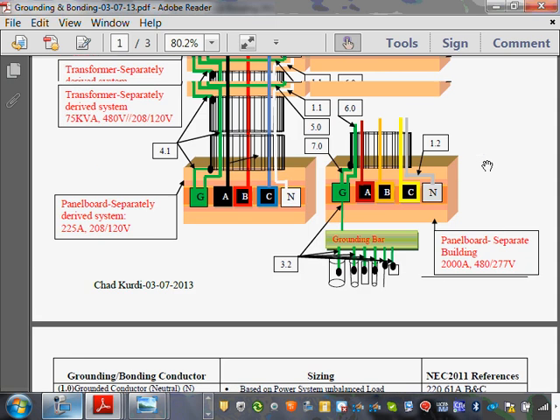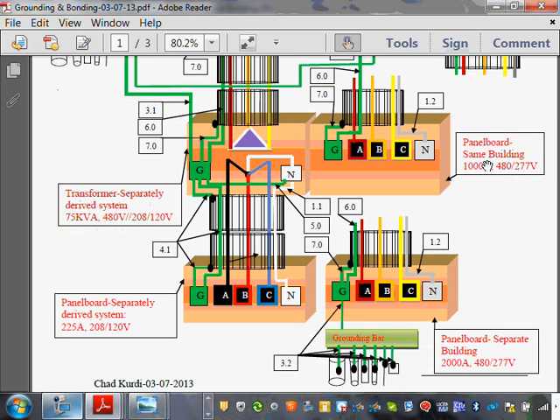So I size my neutral. Now the second thing that we need to do: we bonded the neutral here, and we don't bond the neutral again in the panel. You're not allowed to do that. You can either bond it here or here, but not both. So we bonded the neutral here, we don't bond them here, we keep them separated. Then we size the neutral. Then you have to pull that little wire, called 4.1, the conductor coming right through. Bond the conduits from one side at least, or both. Better both. And you bring it here.